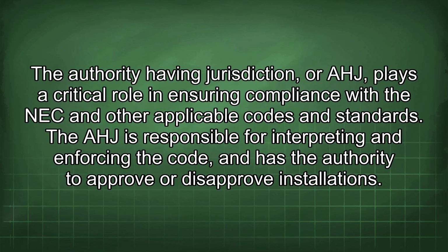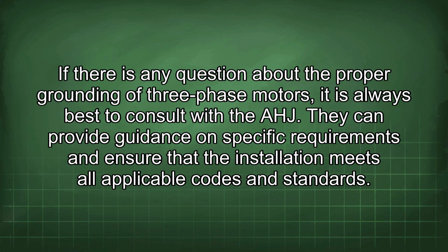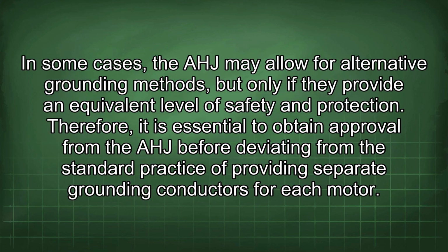The authority having jurisdiction, or AHJ, plays a critical role in ensuring compliance with the NEC and other applicable codes and standards. The AHJ is responsible for interpreting and enforcing the code, and has the authority to approve or disapprove installations. If there is any question about the proper grounding of three-phase motors, it is always best to consult with the AHJ. They can provide guidance on specific requirements and ensure that the installation meets all applicable codes and standards. In some cases, the AHJ may allow for alternative grounding methods, but only if they provide an equivalent level of safety and protection. Therefore, it is essential to obtain approval from the AHJ before deviating from the standard practice of providing separate grounding conductors for each motor.